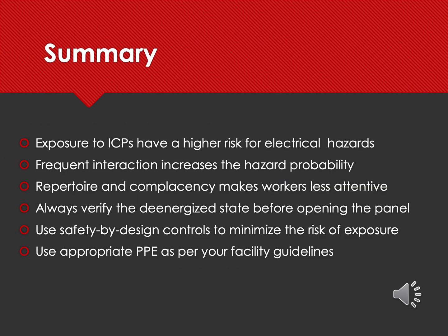So in summary, unlike other electrical equipment, industrial control panels pose a higher risk of electrical hazards, primarily due to 2 reasons. One, various voltage levels inside the panel. For example, a person may be trained on a low voltage system up to 1000 volts. If the panel has a variable frequency drive which is rated for 4160 volts, he or she may be exposed to that higher risk without intention, okay?